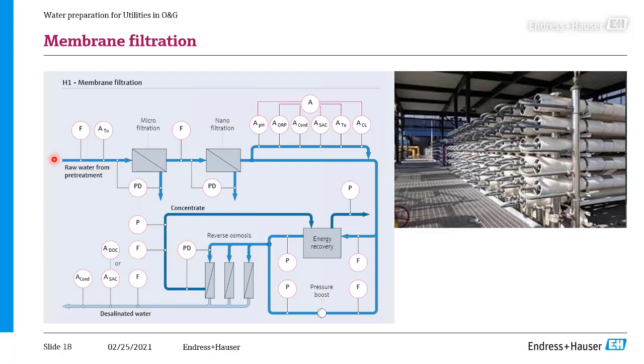So the raw water comes from the pretreatment. Then there's a first microfiltration, a nanofiltration, and here again we check some quality parameters. Important is, of course, that there are no particles, and that chlorination takes place, so we do not have biofouling, or bugs growing on the surface of the membranes, because then they could not do their job anymore. Therefore, chlorination is very important.